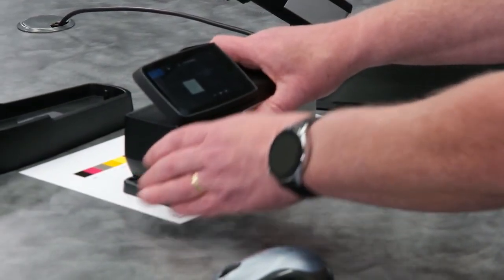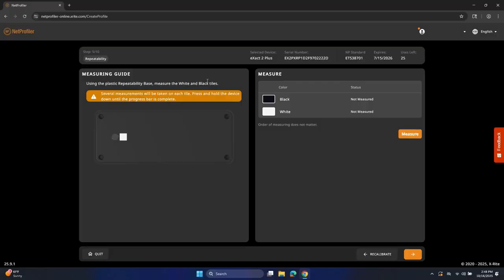Okay. It says in the orange there, several measurements will be taken of each tile. Press and hold the device until it's done. Okay? So I'm going to start measuring. I need it to stay in place, so I don't want it to move. It's going to do 12 measurements of that white tile. And then when it's done with those, I will repeat this process for the black.